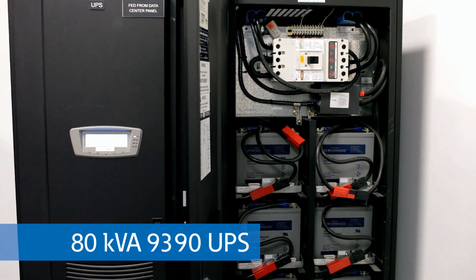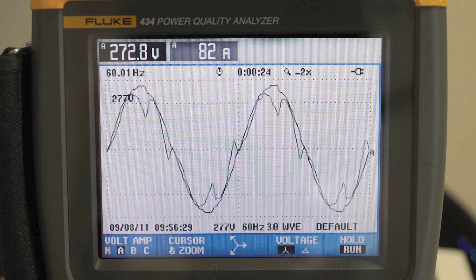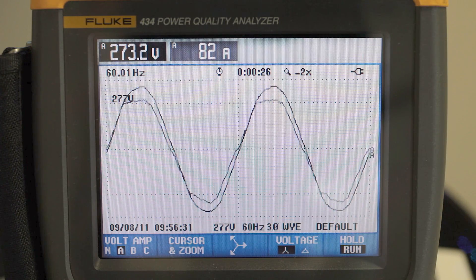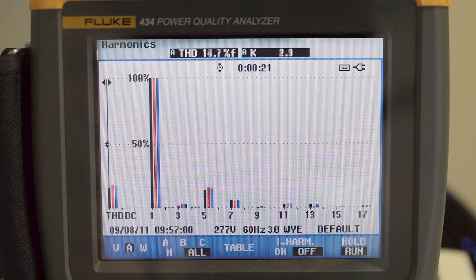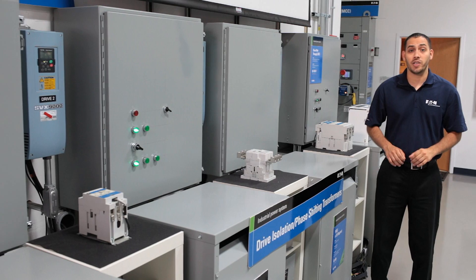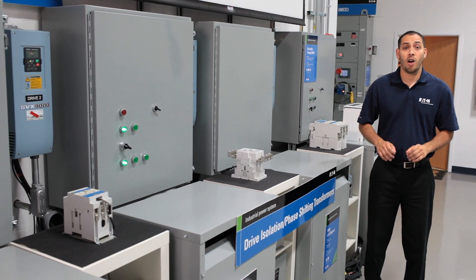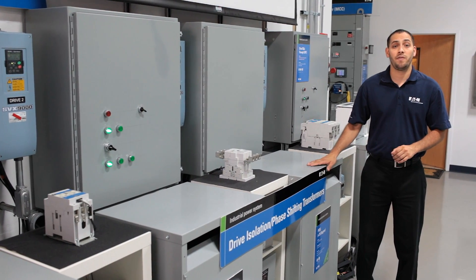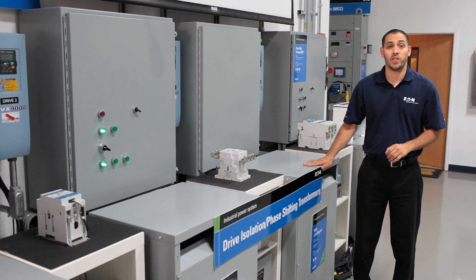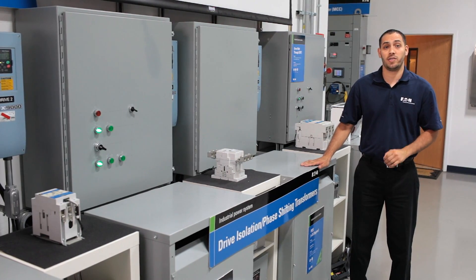Our 9390 and 9395 UPSs feature an active rectifier built into the equipment, allowing continuous active harmonic correction. Finally, a third solution is the use of special transformers. Harmonic mitigating transformers and phase-shifting transformers can be used to cancel the harmonic currents.